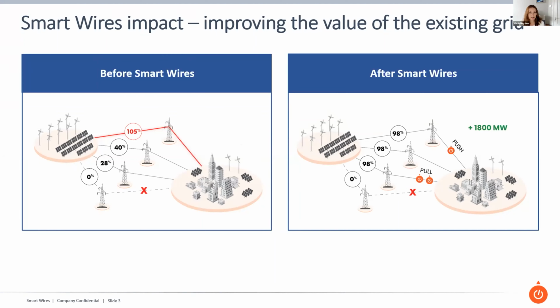And what we see here is quite a typical situation where one line, which is pretty low impedance relative to the other circuits, is carrying the majority of the current and is in fact getting overloaded. And this then causes a bottleneck on the grid, or a constraint as it's often called, or congestion. And the problem is, once you start hitting this bottleneck, you can't really increase the generation in the west, because the more you try and transfer across from west to east, the more you're going to overload that circuit. You can see on the other circuits, though, that there's plenty of spare capacity on those.